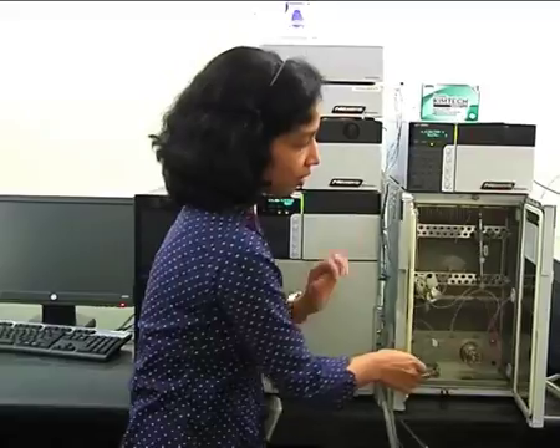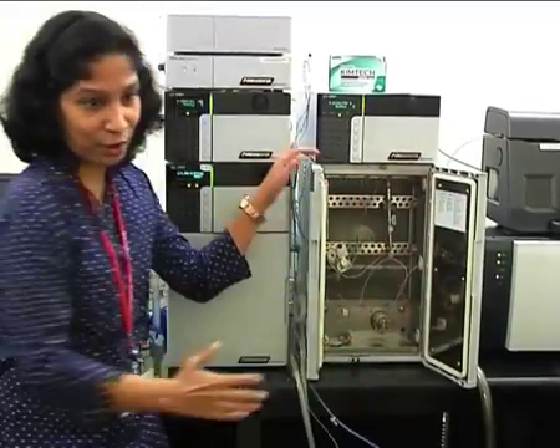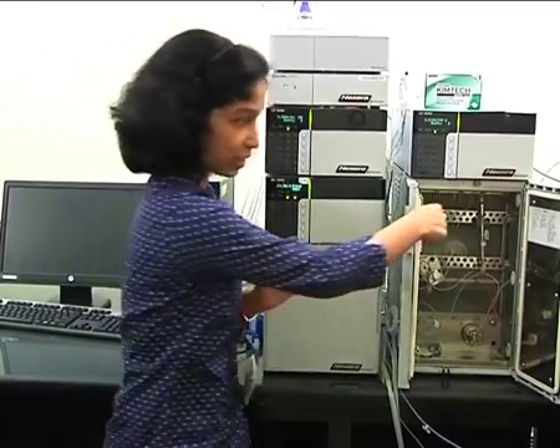This is a column oven, a fairly large area, so that you can accommodate smaller as well as bigger length columns. And there are two types of column ovens available. One is called forced air circulation, which is this type. The other one is called a heat block column oven. In a heat block type, there is a heated block on which your column resides, generally an aluminium block, and it transfers heat to your column.